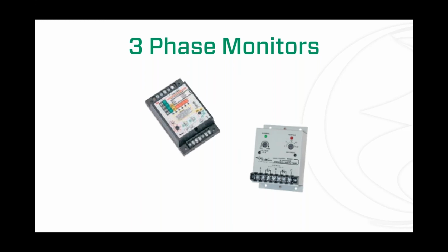Maybe nobody thinks any of the equipment is working, but if the lift station is called to come on, your pumps are, and if you're missing a phase for whatever reason, that pump is going to try to run on just 2 phases of power instead of 3. Or sometimes you might have an electrical loss or a drop on one of your phases, or all of them. These guys are going to monitor all that.